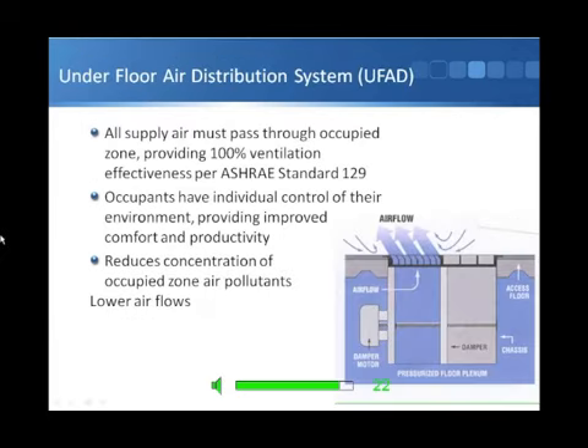And we can look at more efficient air distribution systems. Underfloor air distribution is one, using the zone underneath a raised floor, which brings air in, and that goes up through the sort of diffusers I've shown here, through a floor box, and that allows air to stack up through the space, passing through the occupied zone, removing concentrations, removing heat from office spaces, and taking that away where it can either be rejected or recovered if it's useful. So underfloor air distribution systems are a fairly new idea, but they have been applied in quite a few buildings in the UK and the United States.